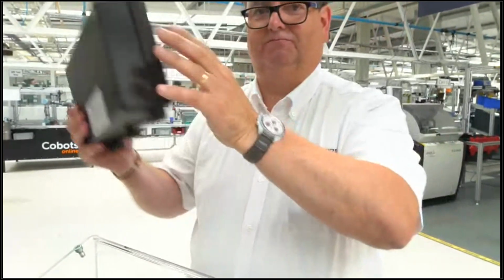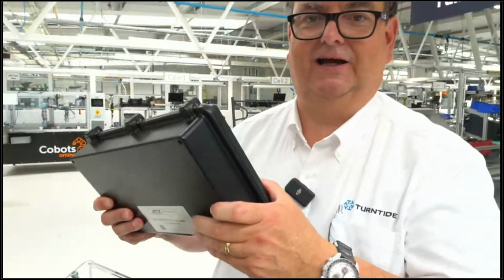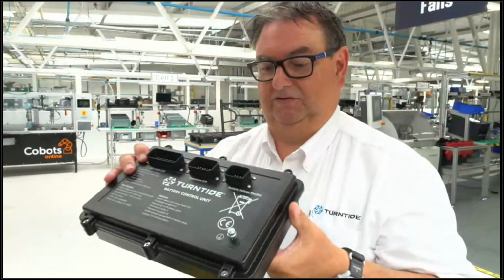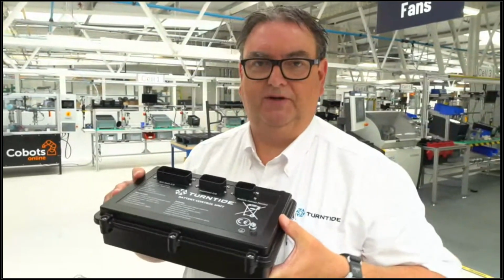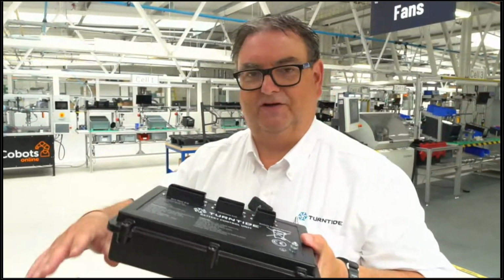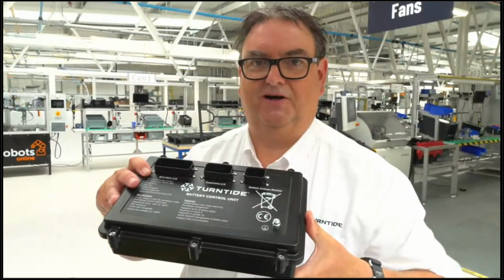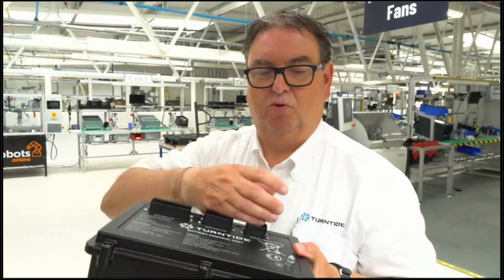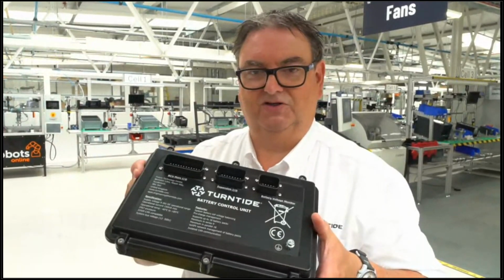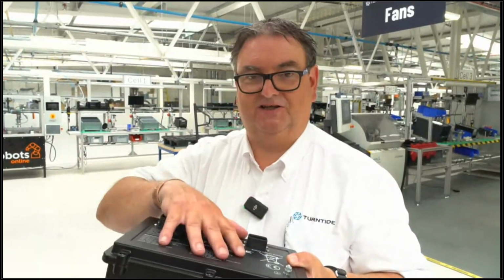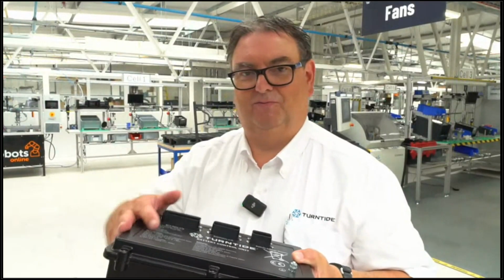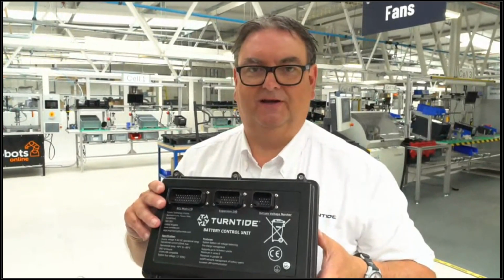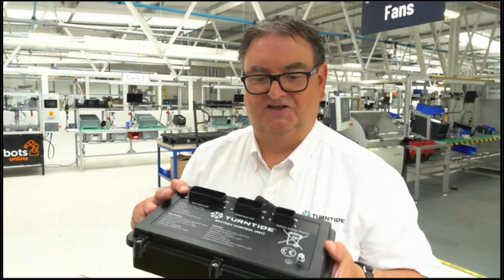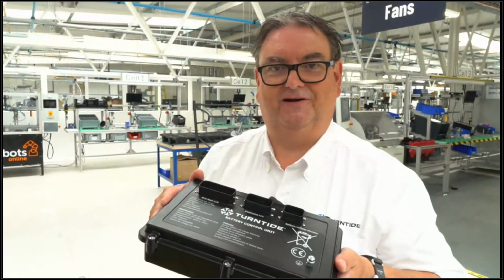This gives flexibility - it can be put in various places on the application, increasing flexibility. It also means that should there be an issue with the battery control unit, you don't have to return any of the battery packs. All of the electronics, the smart stuff, is contained here. This can be returned, we can ship out a spare one with next day delivery, simple plug and play, and your system could be up and running again. Our previous battery packs had the master controller in each of the modules - we've taken that out and separated it. From ease of system integration, serviceability, maintainability, and spares policy, going down this route makes it far easier to work with the batteries.